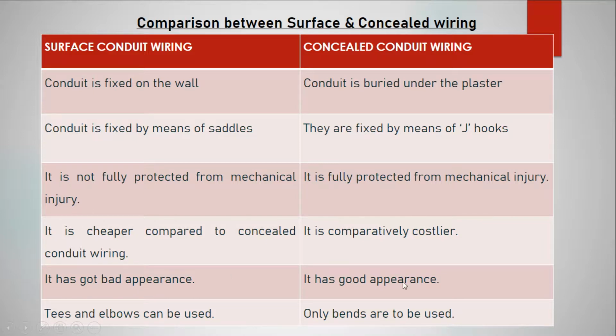Surface conduit wiring has a bad appearance because it is seen outside. It does not look good, but concealed conduit wiring nowadays gives a very good appearance. And in the surface conduit wiring system, wherever you want to bend the cables, you have to use bends, T's and elbows. There is a PVC structure called a T structure, and elbows are also available. Elbows are around 90 degrees. So bend structures are available. If you want, you can go to a hardware shop and check. So T's and elbows are used there, whereas in concealed conduit wiring only bends are used.